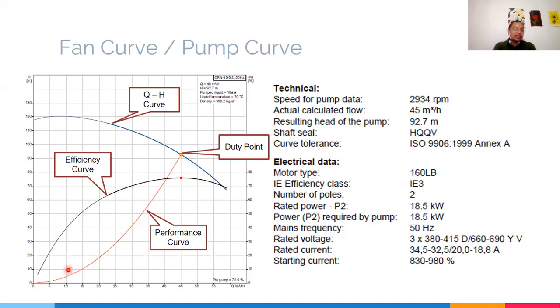And the red line here, this is your performance curve. So from startup to duty point, so pagka inon mo, if you turned on your pump, it would go slowly, right? It will speed up from zero. It will speed up to its required rotational speed. So while it's speeding up, this is the path that the pump will take. Okay? Ito yung performance curve niya. So without changing the criterias, ito yung head. Okay, yung head mo, ito yung efficiency mo, at saka ito yung performance mo. So when you run the pump, this is the expected performance of the pump. This is your duty point.